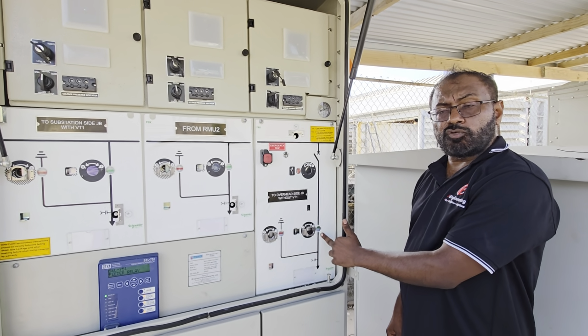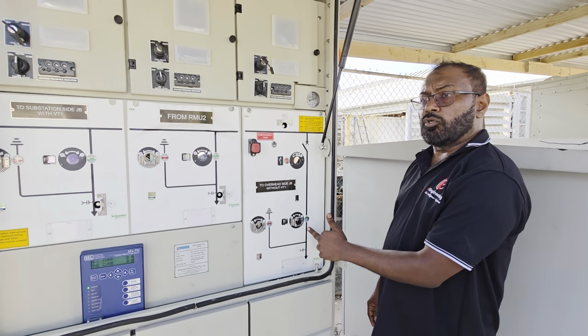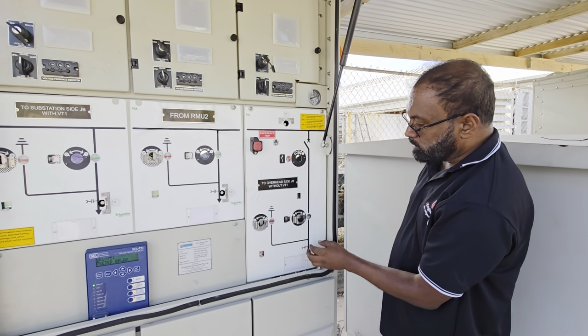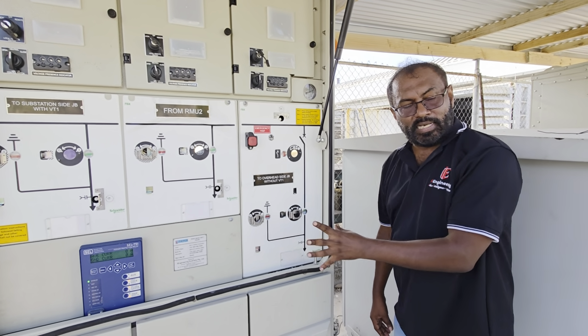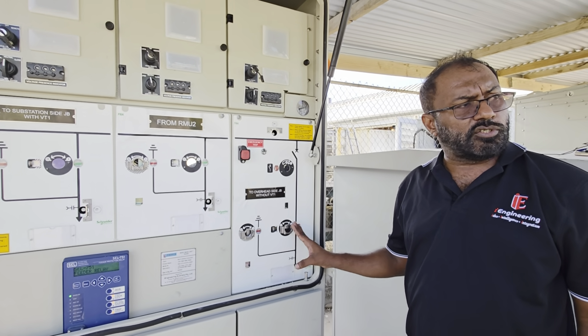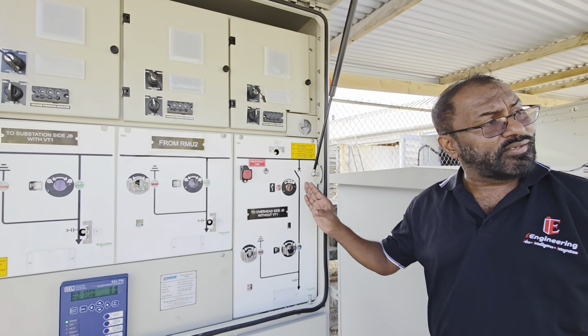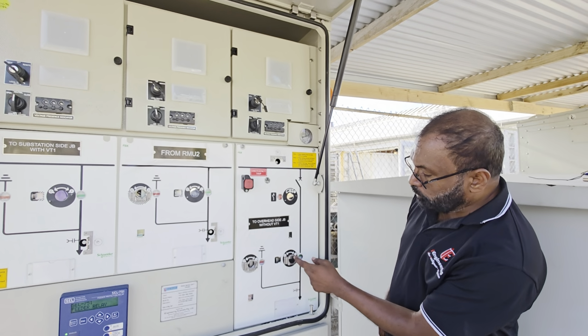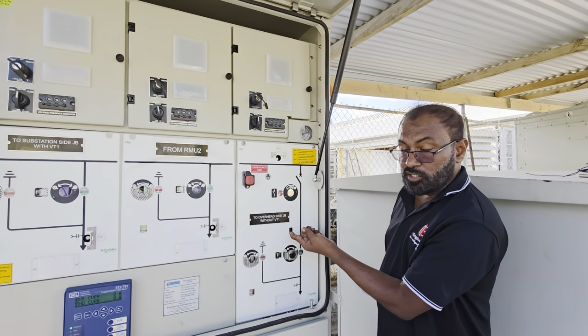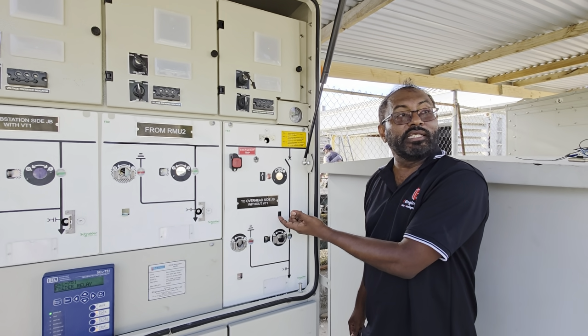Remember I said this is a disconnect switch? You cannot now close it because the circuit breaker is closed. If you did, there will be arcing and you will damage the disconnector. It's not supposed to be opened or closed when it's live. So if you try to close this now, can you see it's locked? It won't let it close.